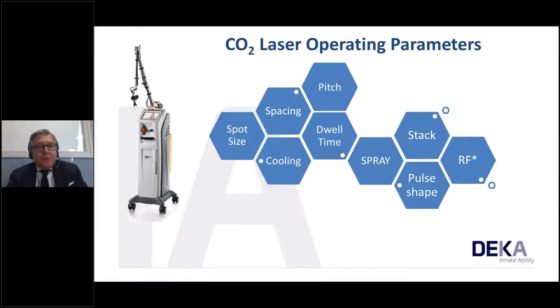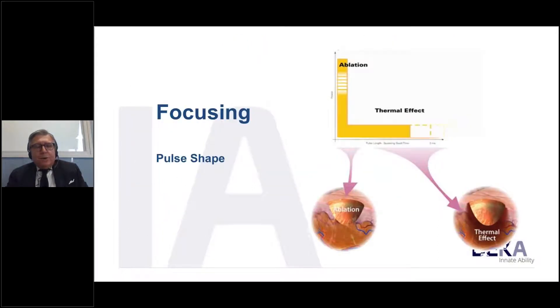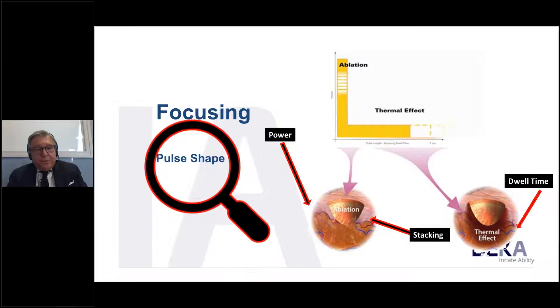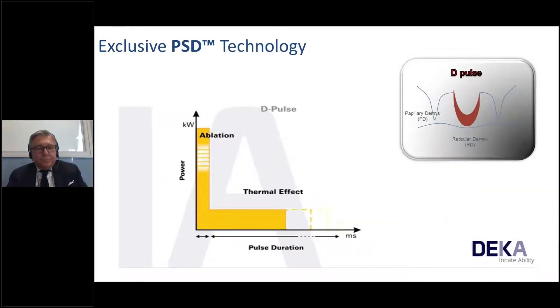Focusing on pulse shape: the first two parameters, power and stacking, are strictly related to ablation capability. The third, dwell time, relates to thermal diffusion. A fourth parameter, pulse shape — particularly D pulse used in 90% of fractional treatments — allows deeper penetration and stimulation and micro-ablation at deeper layers. The great capability of the D pulse mode to go into depth and create a very deep ablation crater is clearly demonstrated.